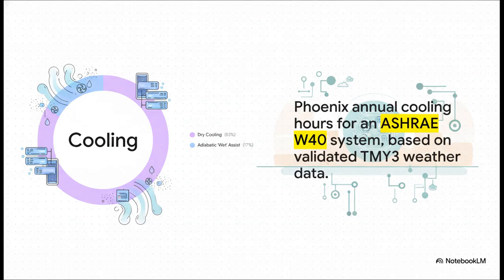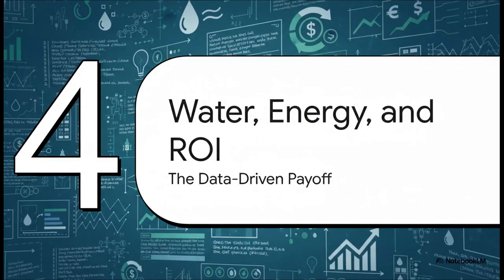For 83% of the entire year, this warm water system can run completely dry, meaning it uses zero water. It's only during those absolute peak summer hours, that other 17%, that it needs a little help from a very light mist of water to boost its cooling power. Making this huge shift from a cooling system that's mostly wet to one that's mostly dry has a dramatic, positive impact on the three things every data center operator and investor cares about: water, energy, and return on investment.